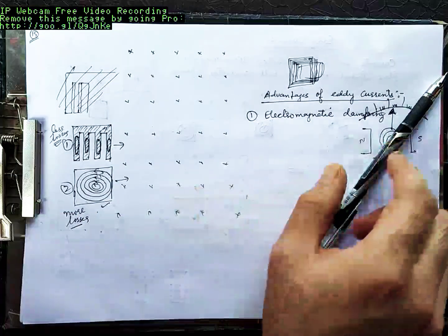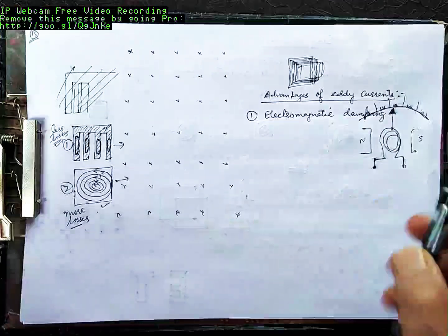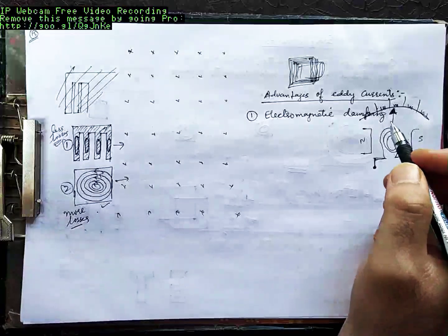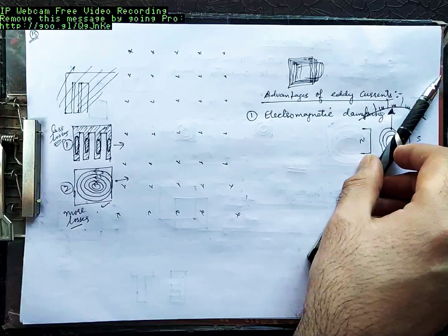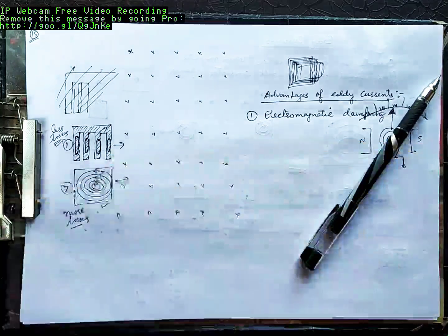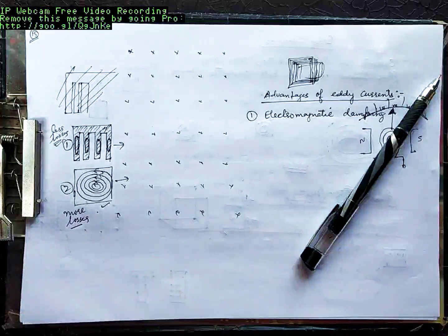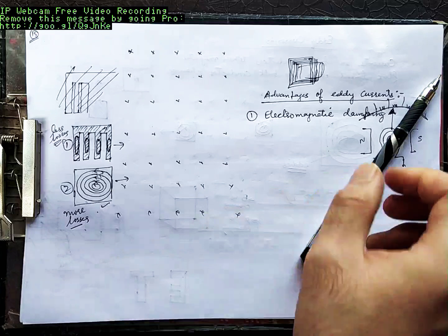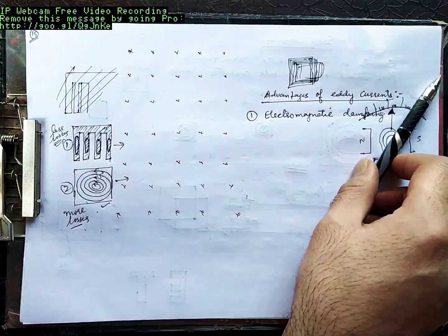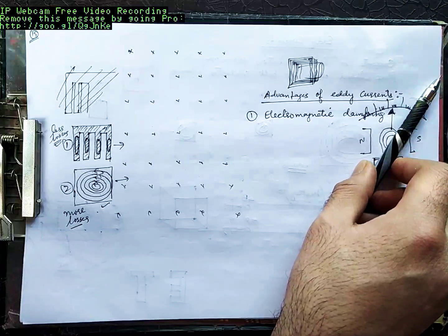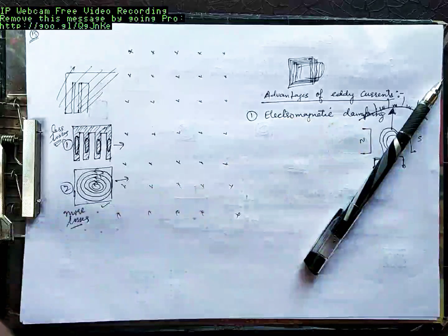But do we want our measurements to be oscillating, or we want them to be fixed at one point? We want them to be fixed at one point. So this would have oscillated without damping here. This would have oscillated and finally settled down to the value. But we want this value to be exact and to be very fast. For that, we do not want these oscillations of this coil here. We want these oscillations to die very fast. For that, we use electromagnetic damping.